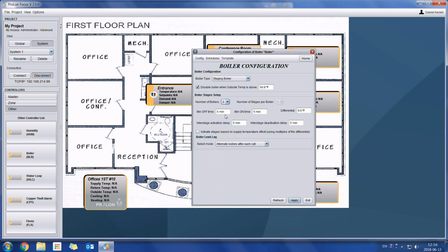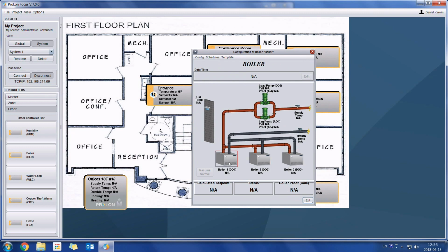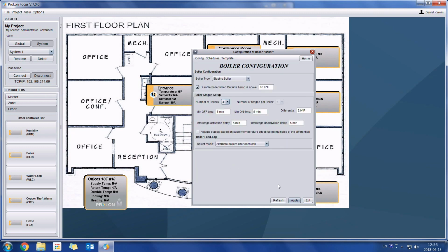We could have 3 single staged boilers right there, or 4 single stage boilers. So the boiler controller has 4 digital outputs, so we can do any combination of up to 4. Obviously here we have the minimum on time and minimum off time to prevent short cycling, and we also have a lead lag system on our boilers, so in case one boiler fails, the other ones are going to turn on.